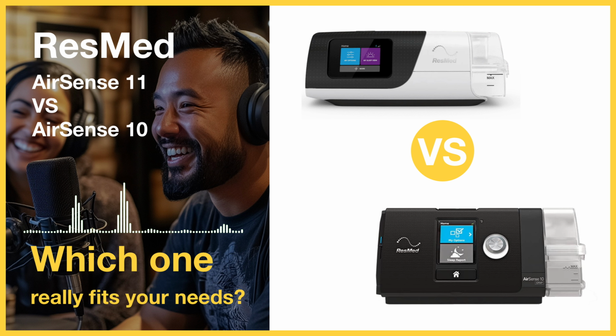Things that make it easier to actually use the device every night, like autoramp and EPR. Both machines have those key comfort features. Autoramp starts the pressure low when you first put the mask on, helping you fall asleep easier, then gradually ramps up to your prescribed pressure. And EPR, expiratory pressure relief, lowers the pressure slightly as you exhale, making breathing out feel more natural, less like you're fighting the machine. Big comfort factor for many people.